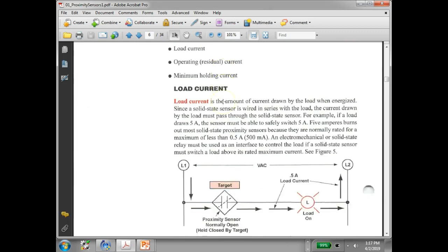They're only 2 wires. Load current—everybody okay with that? So this is how much the sensor should draw when it's energized. I don't think you did this in motor controls, but here you're actually going to have to break the circuit and measure this current.